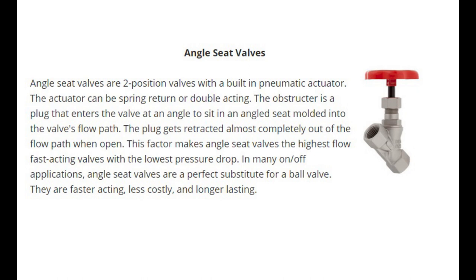Angle seat valves are two-position valves with a built-in pneumatic actuator. The actuator can be spring return or double acting. The obstructor is a plug that enters the valve at an angle to sit in an angled seat molded into the valve's flow path. The plug retracts almost completely out of the flow path when open, making angle seat valves the highest-flow, fast-acting valves with the lowest pressure drop. In many on/off applications, angle seat valves are a perfect substitute for a ball valve — they are faster acting, less costly, and longer lasting.